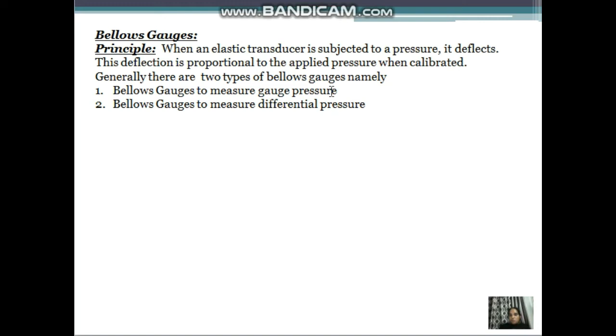Generally we have two types of bellows gauges, namely bellows gauges to measure normal gauge pressure and to measure differential pressure. The bellows element is cylindrical in shape, and the wall of this cylinder is thin and corrugated. The wall of the bellows is about 0.1 mm thick and is made of some springy material such as stainless steel, brass or phosphor bronze. This bellows element is open at one end to receive the applied pressure and is closed at the other end. This other end is usually attached to a rod. In many cases, a spring is placed inside the bellows to enable it to regain its original shape when the applied pressure is relieved. If you see this figure, this is the bellows gauge to measure gauge pressure.